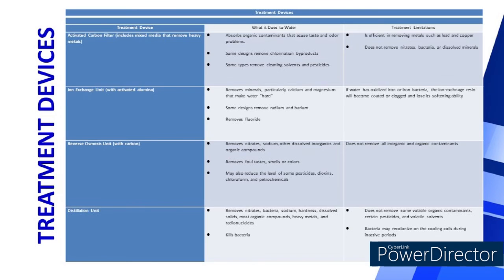If water has oxidized iron or iron bacteria, the ion exchange resin can become coated or clogged and lose its softening ability. Reverse osmosis unit (carbon) — removes nitrates, sodium, other dissolved inorganics, and organic compounds; removes foul taste, smells, and colors; and may also reduce the level of some pesticides, dioxins, chloroform, and petrochemicals. Limitation: does not remove all inorganic and organic contaminants.